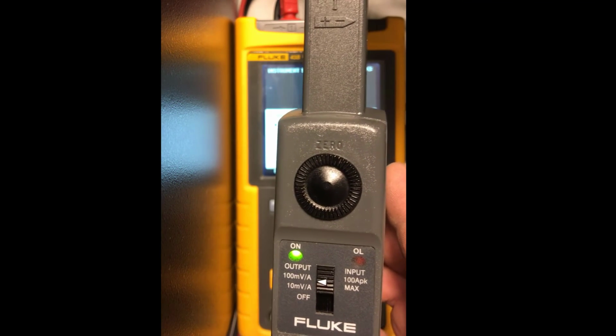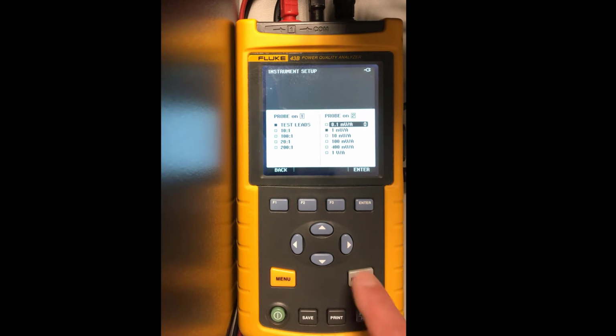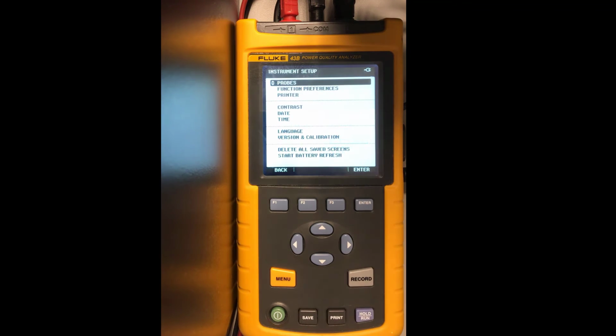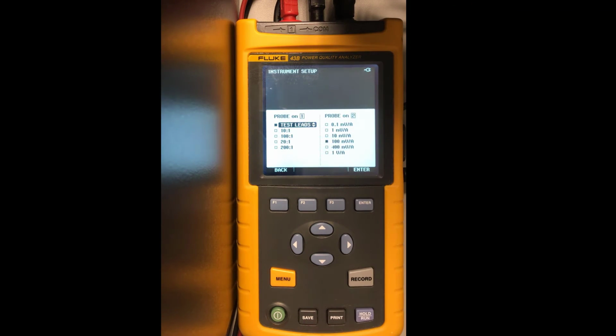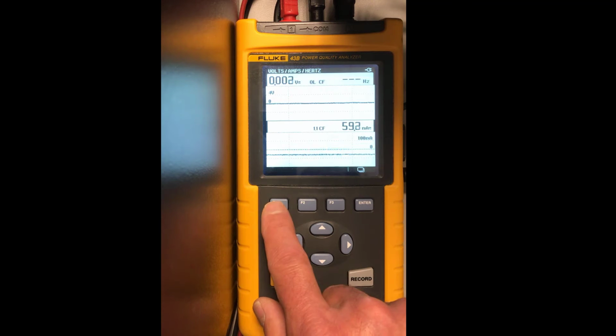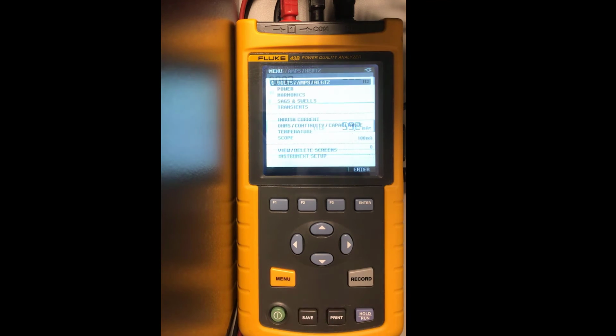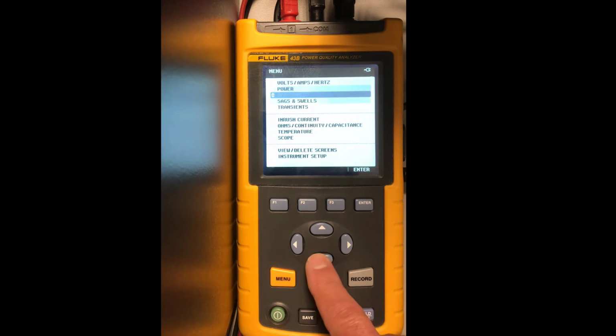Okay, so once that's set up there, what we need to do is go to our power analyzer and set it to the same setting. So notice how we have 100 millivolts per amp here. We have to select that by hitting enter, and I always think it's a good idea to go back in and just make sure that setting was set for the device. So you notice how I just went back into that instrument setup again and verified I have a 100 millivolts per amp. Okay, so once you've done that, then you can just go back in your menus to volts, amps, hertz. Now, in the menu, if you didn't end up back at volts, amps, hertz and some other menu or some other function, just go into menu and take yourself to volts, amps, hertz and hit enter.